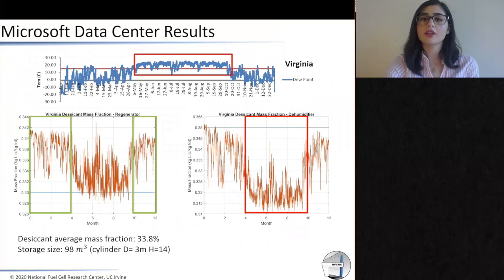There is also another scenario that we can look at involving storage. For example, for a place like Virginia, which only needs dehumidified air for six months between May and October, we can use the rest of the year to produce a strong desiccant and store it in a storage tank. When we need dehumidified air, we use this strong desiccant to produce cold and dehumidified air for our data centers. In this scenario, we are able to provide not only the power needed for our single server rack, but also the cold and dehumidified air needed for that one single server rack.